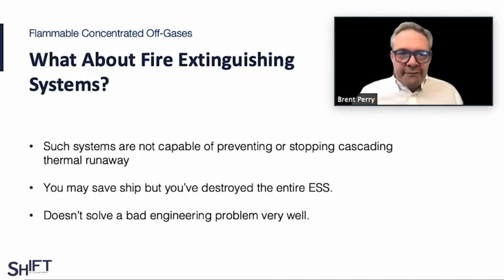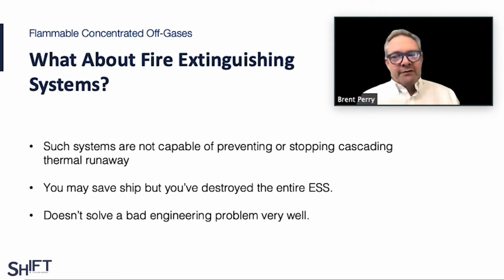Then we deal with the issue of third-party firefighting systems. There are some very effective ways to manage lithium fires. There are some excellent two-part foam systems that can contain a lithium fire. Very expensive to install. Do have some service and maintenance elements that have to be contended with. And then there are conventional firefighting systems, like gas firefighting systems, or foam firefighting systems, or simple chemical firefighting systems, or water mist systems, or sprinkler systems. All of these systems have the problem of durability. If you can't effectively surround the lithium fire with something like a two-part foam, there's almost no way to make sure that you have enough reservoir material to continue to extinguish a fire for the durability that it can have.